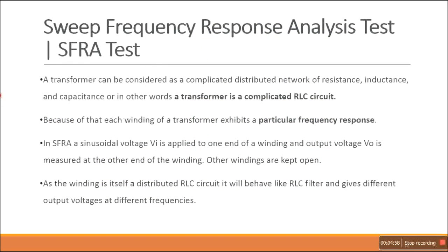SFRA test, or the sweep frequency response analysis test. A transformer can be considered as a complicated distributed network of resistance, inductance, and capacitance. Or in other words, a transformer is a complicated RLC circuit. Because of this, each winding of the transformer exhibits a particular frequency response.